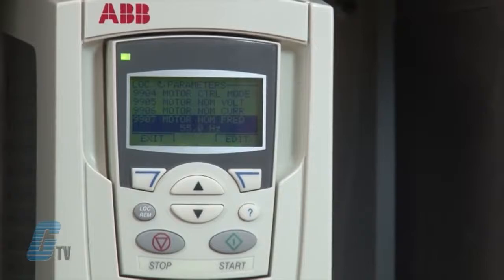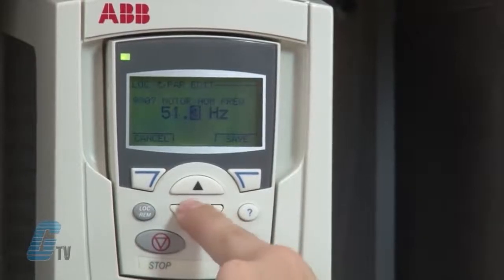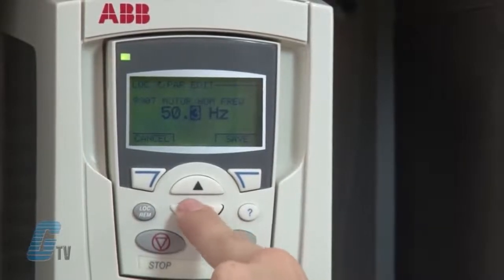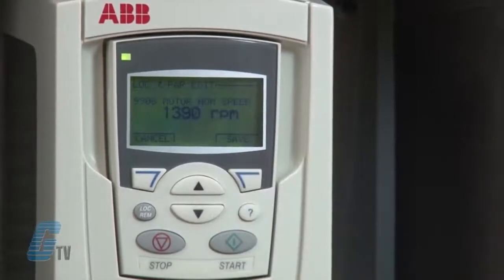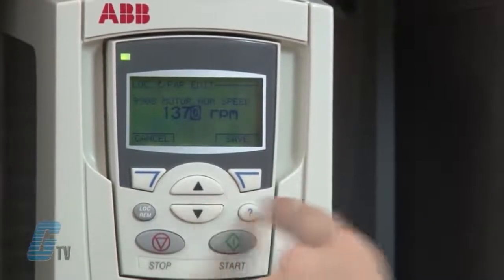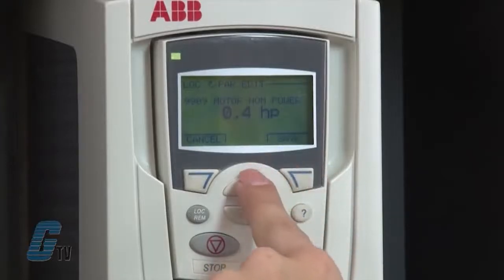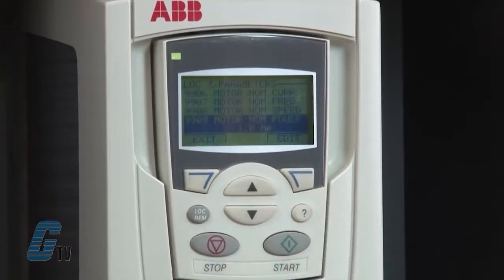Next, I will go to parameter 9907 and enter the motor nominal frequency, which is 50 hertz in this case. Next, I will go to parameter 9908 and enter the motor's nominal speed, which is 1370 RPM. Next, I will go to parameter 9909 and enter the motor nominal power, which is 1 horsepower. At this point, I have completed the entry of my motor nameplate data.